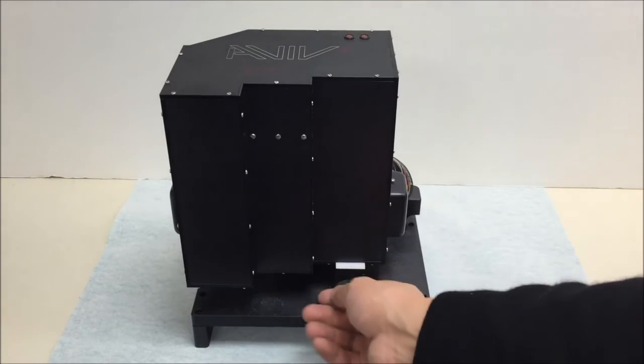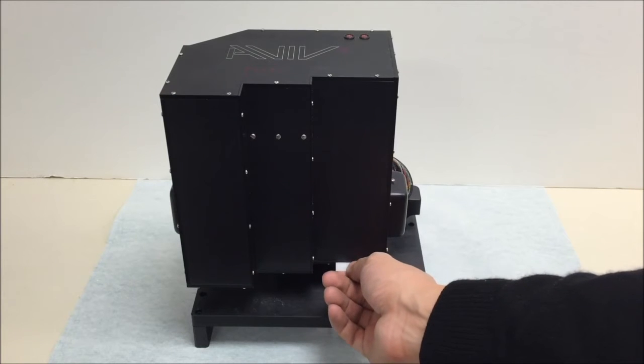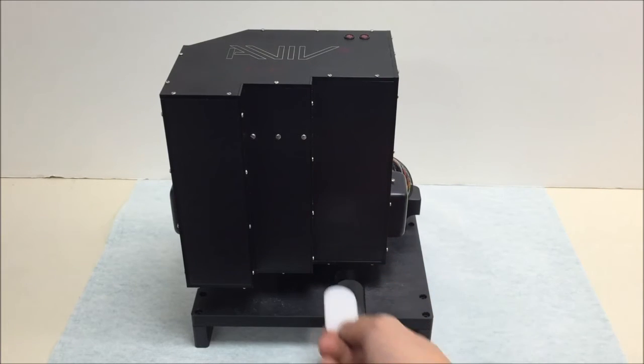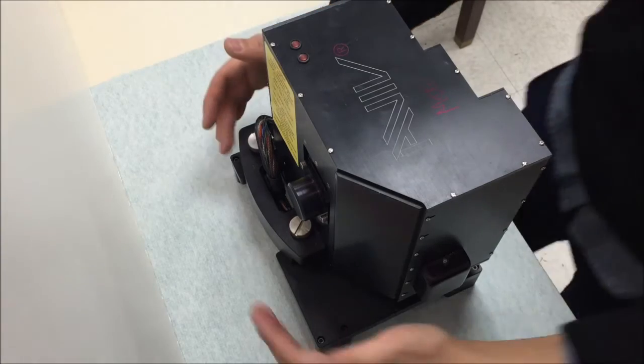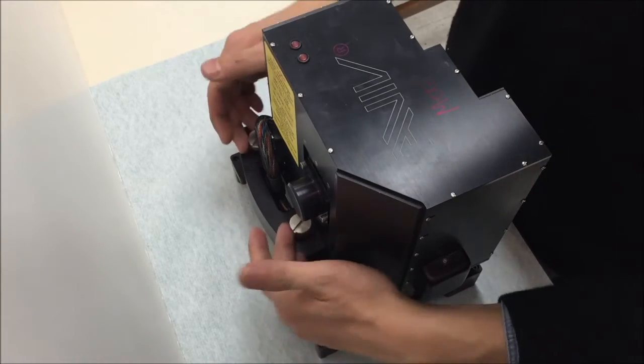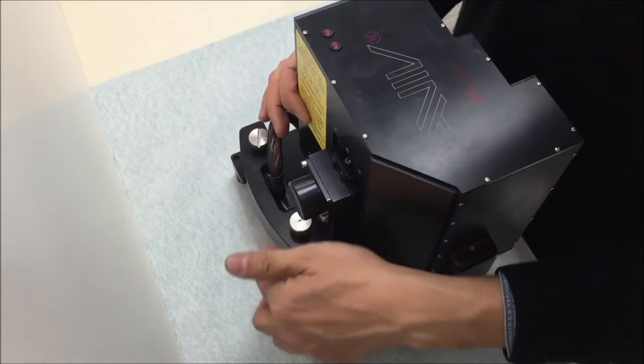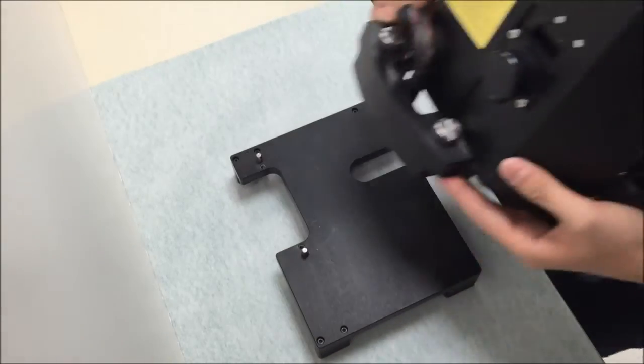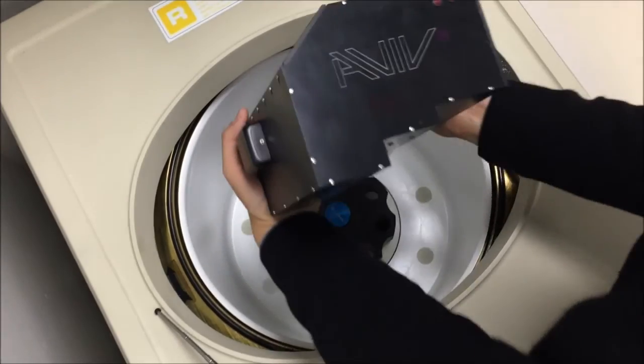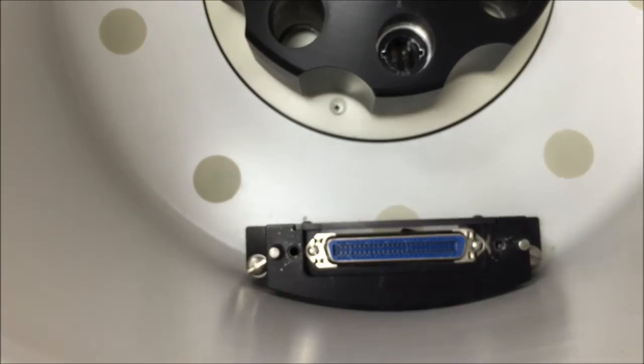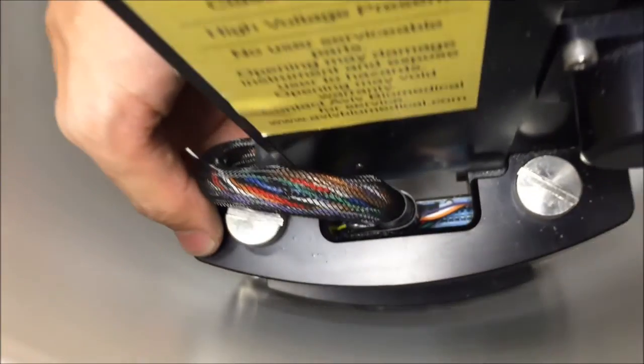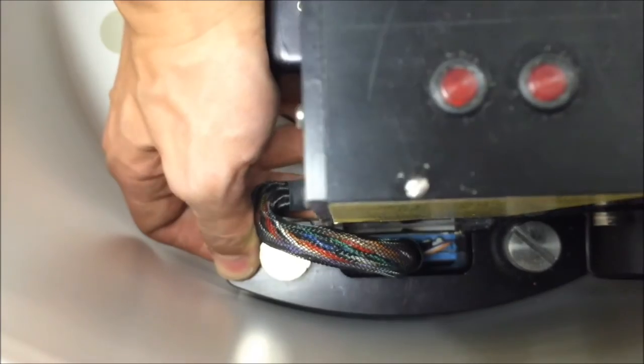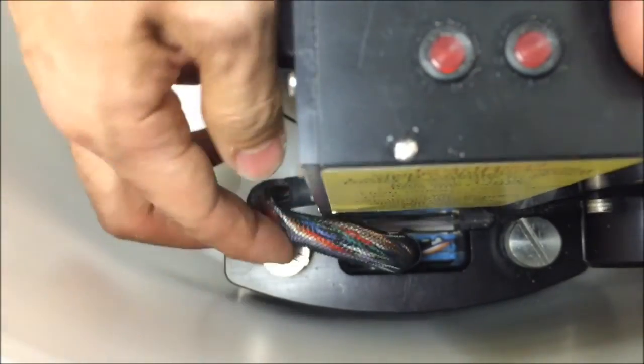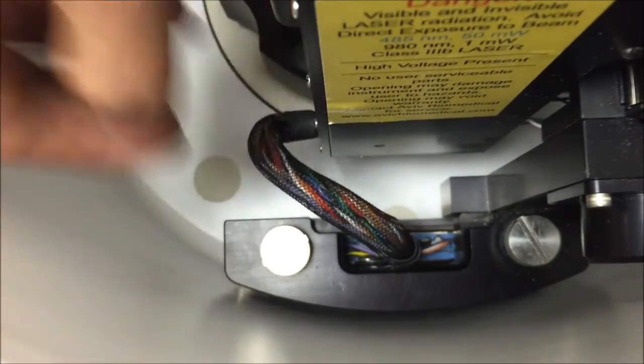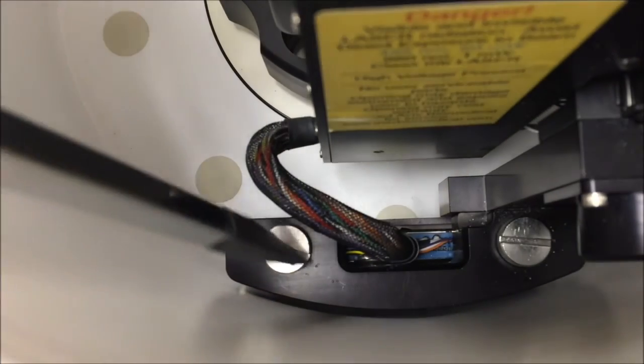The optics box is kept on the storage plate. Pull out the dust cover. Remove the optics box from the storage plate. Align the box with the electrical connector and guide poles on the mounting bracket. Push it to make the box sit properly. Tighten the screws by fingers and fix them with a screwdriver.